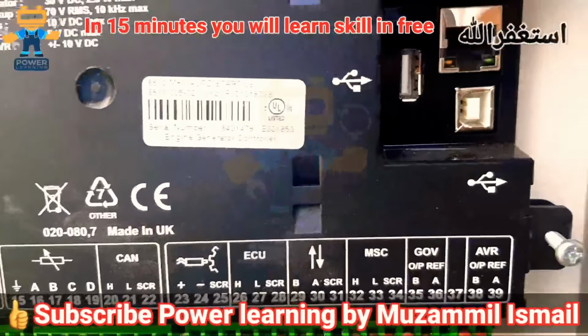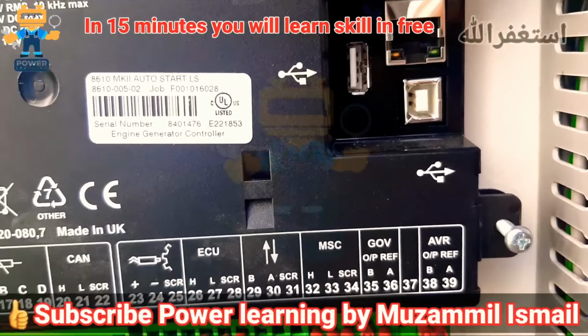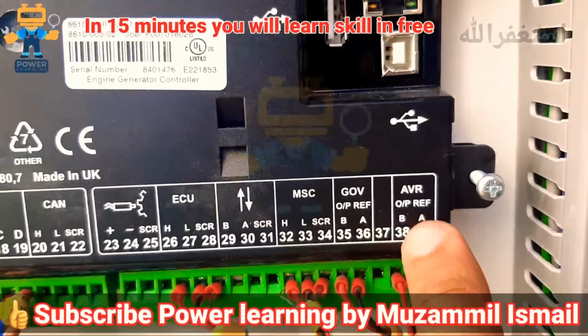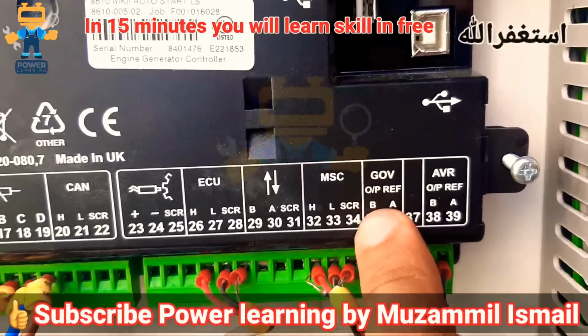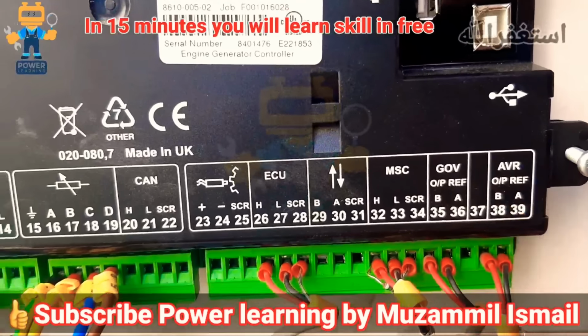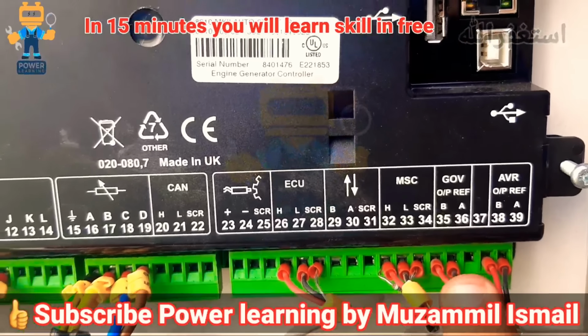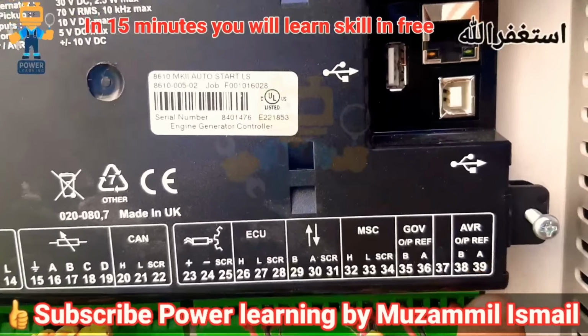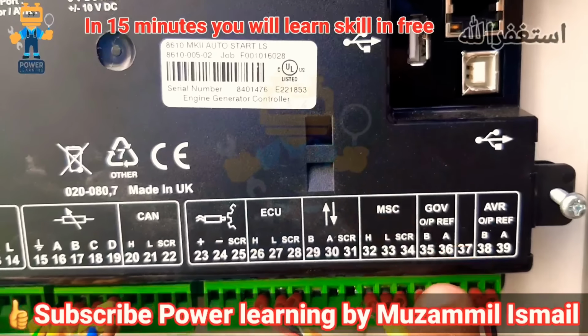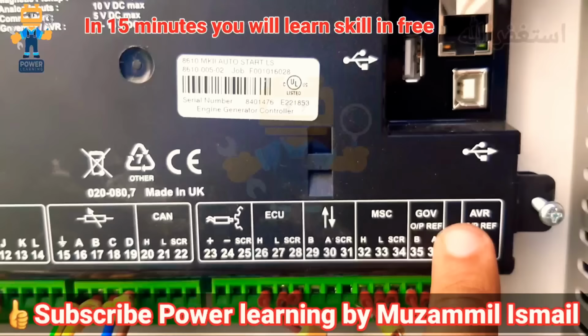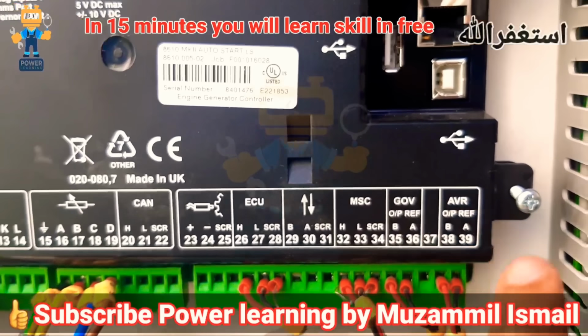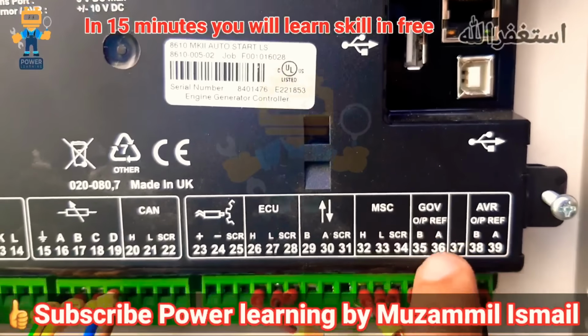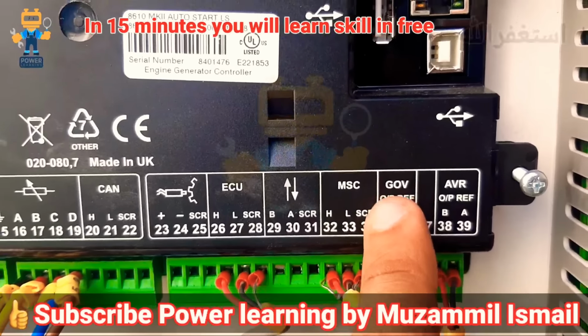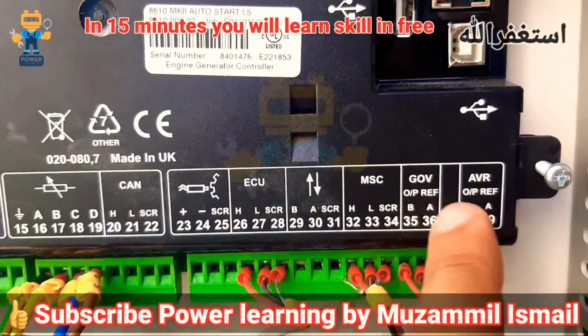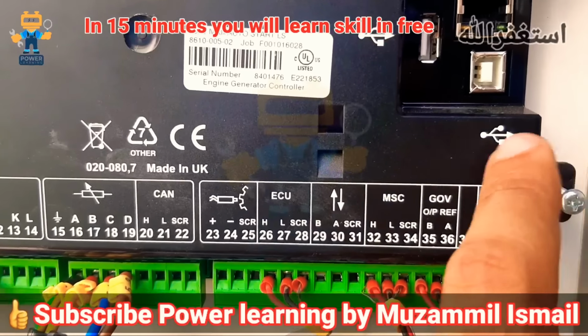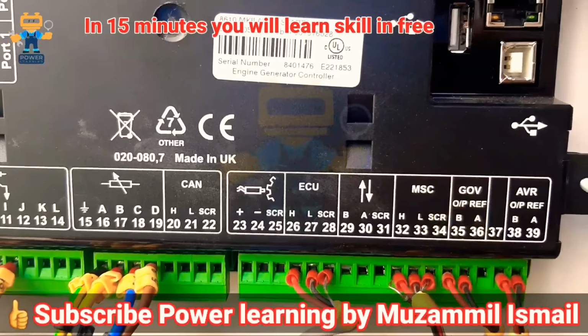this cable. After that here we have governor and AVR. This is very important. Governor and AVR, we are using to control the engine speed, and AVR for voltage control, because in synchronizing, as you know, we have to control the generator frequency and generator voltage. So these are working as analog outputs from 0 to 10 volt. These 2 are giving analog outputs to our governor and to the AVR as per required load for increasing and decreasing the voltage and increasing and decreasing the frequency.